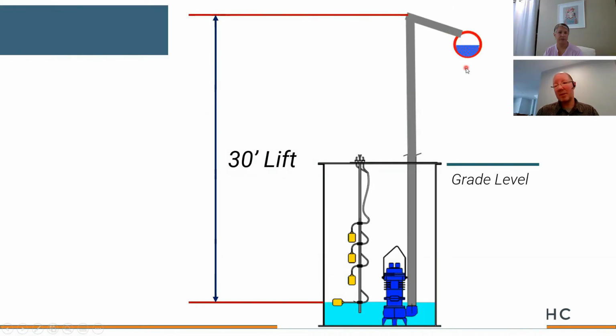And the reason we see sump and sewage on commercial is we might have some loads that are below our city connection point. Okay, they might be down in a parking structure, 1 or 2 floors down. And in order to get water out of the bottom of the building, the only way to do it is to physically lift it. So that's the pump's job.